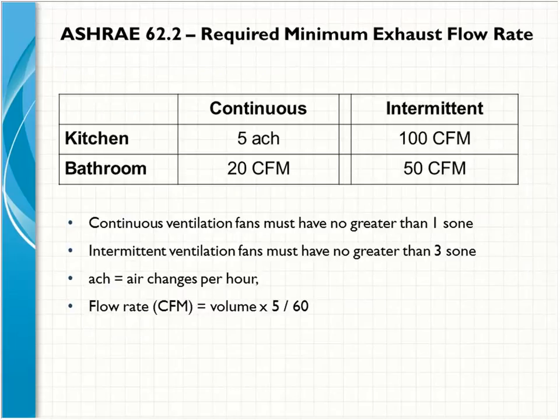So the requirements here for bathroom fans are that they're capable of doing 20 CFM continuously or 50 CFM intermittently, and there are some zone ratings that go along with that as well. As was pointed out earlier, the intermittent requirements are 3 sones or less, and for continuous ventilation equipment, we want to keep it at 1 sone or less. Those are, of course, rated, and actual installs can have an impact on how noisy a piece of equipment is.